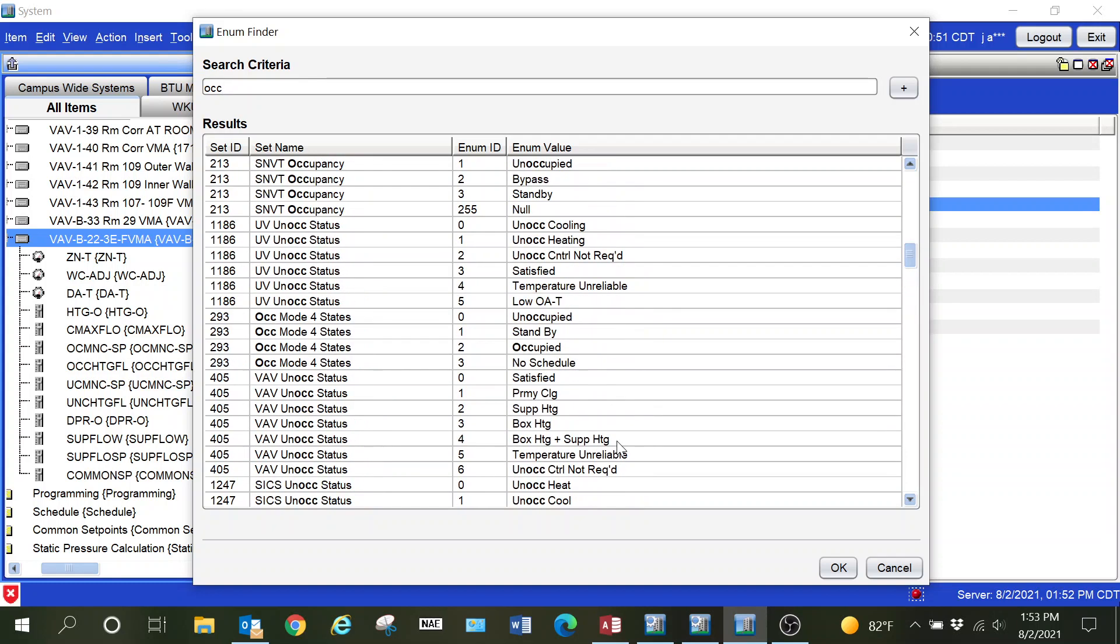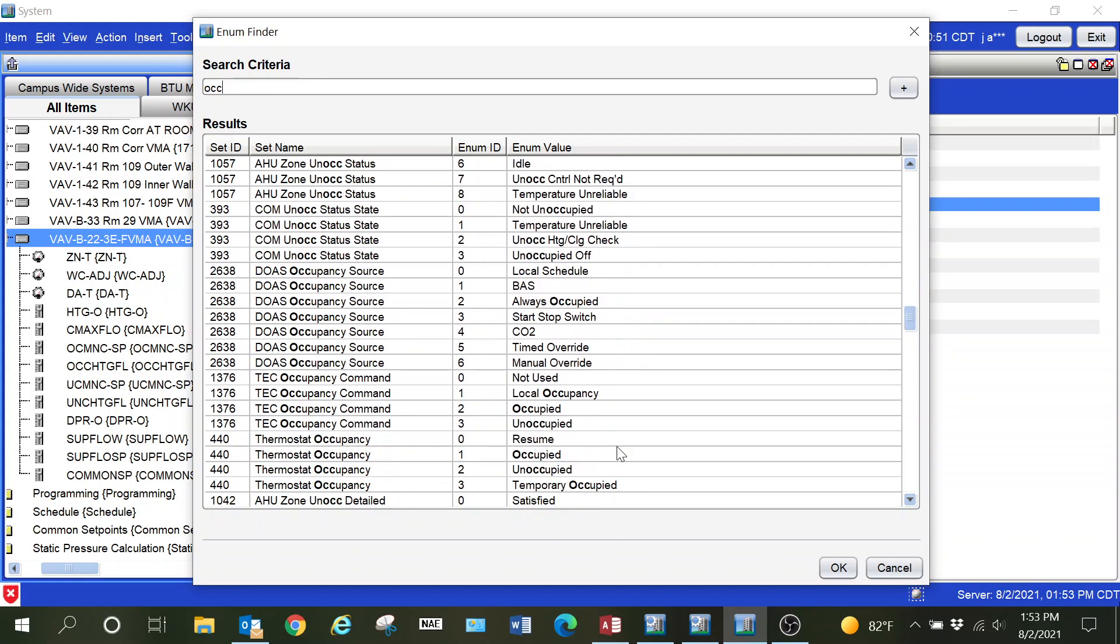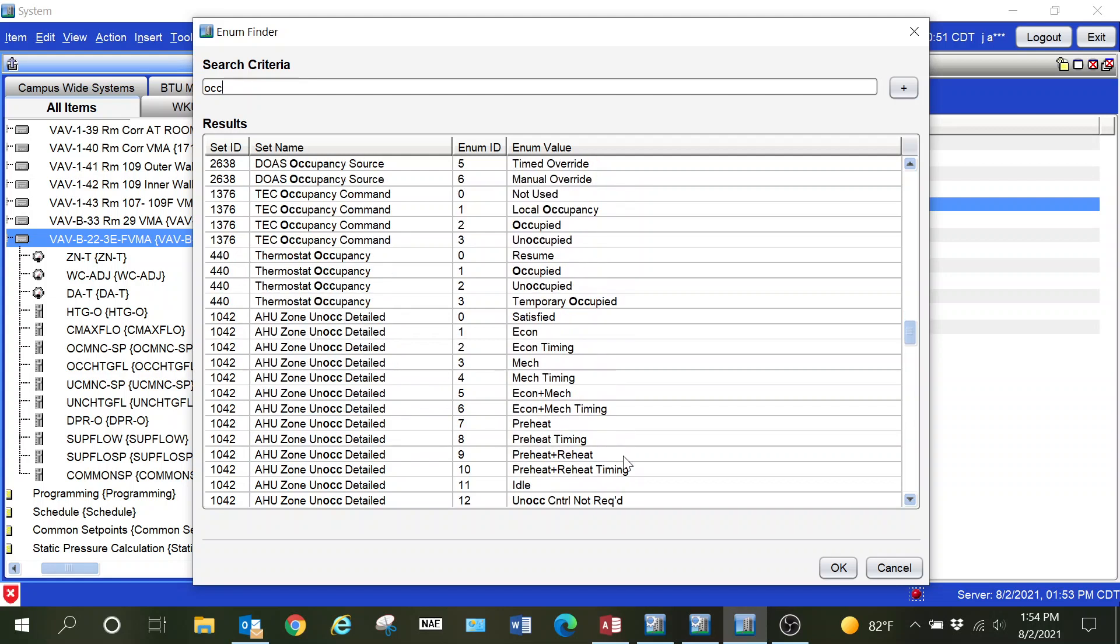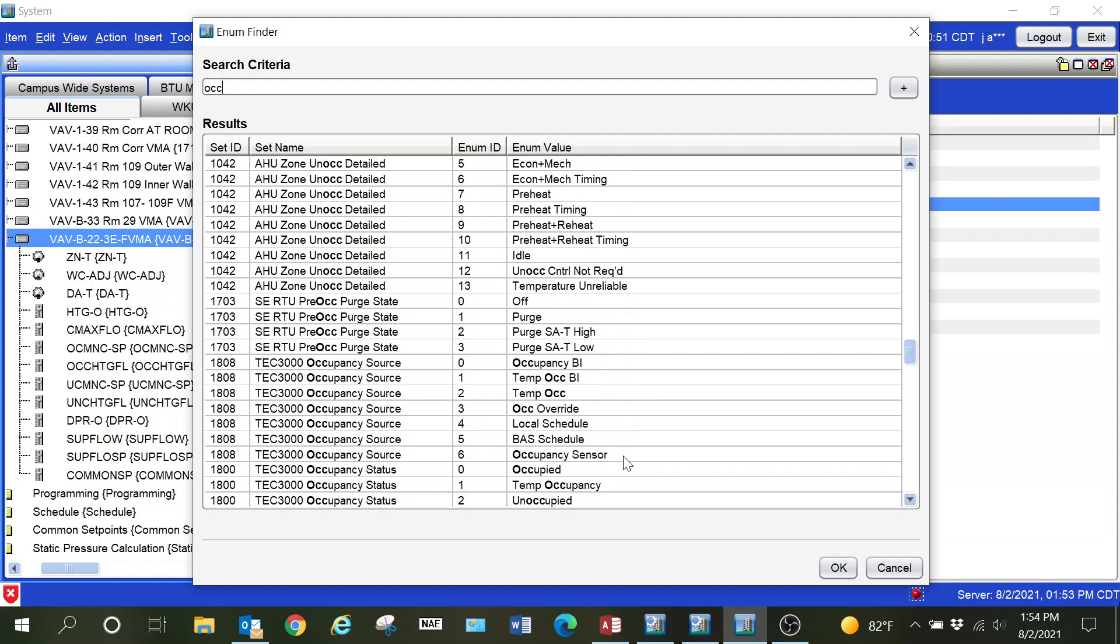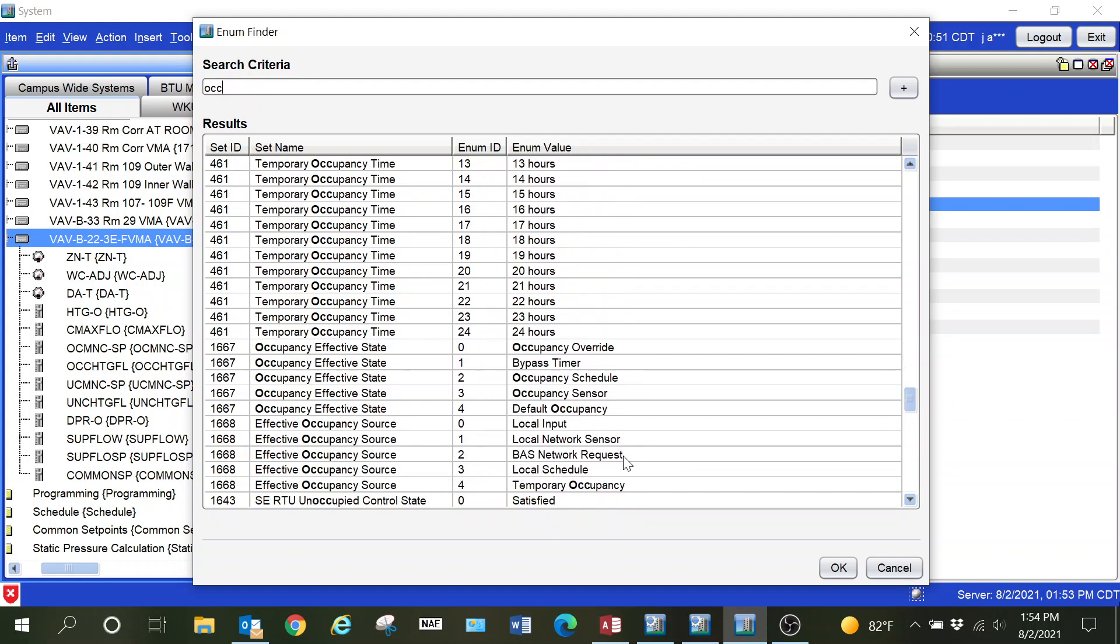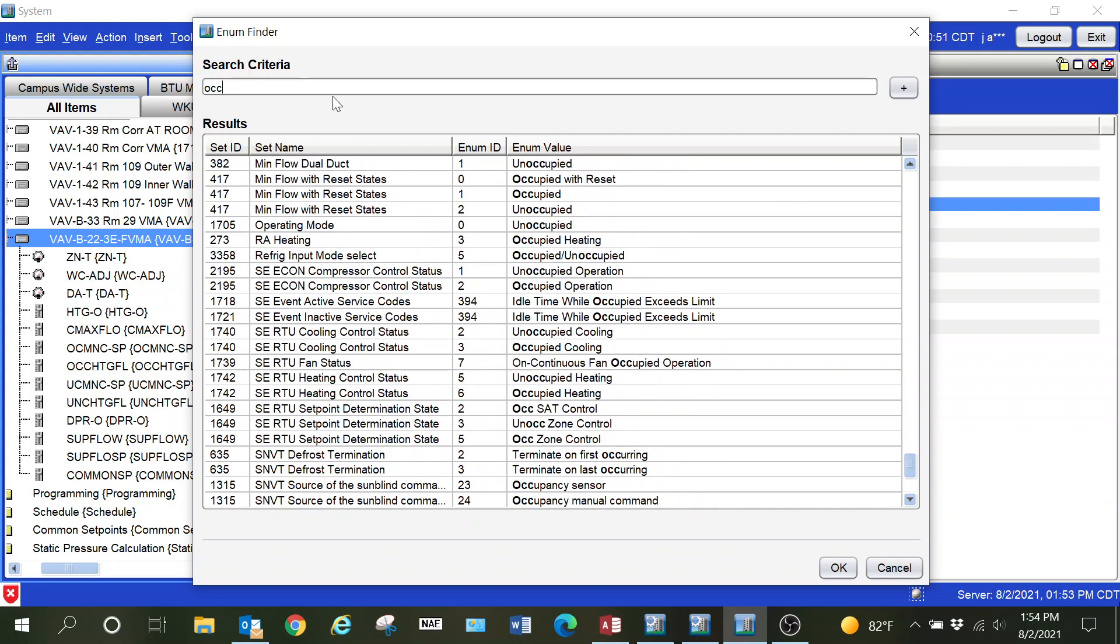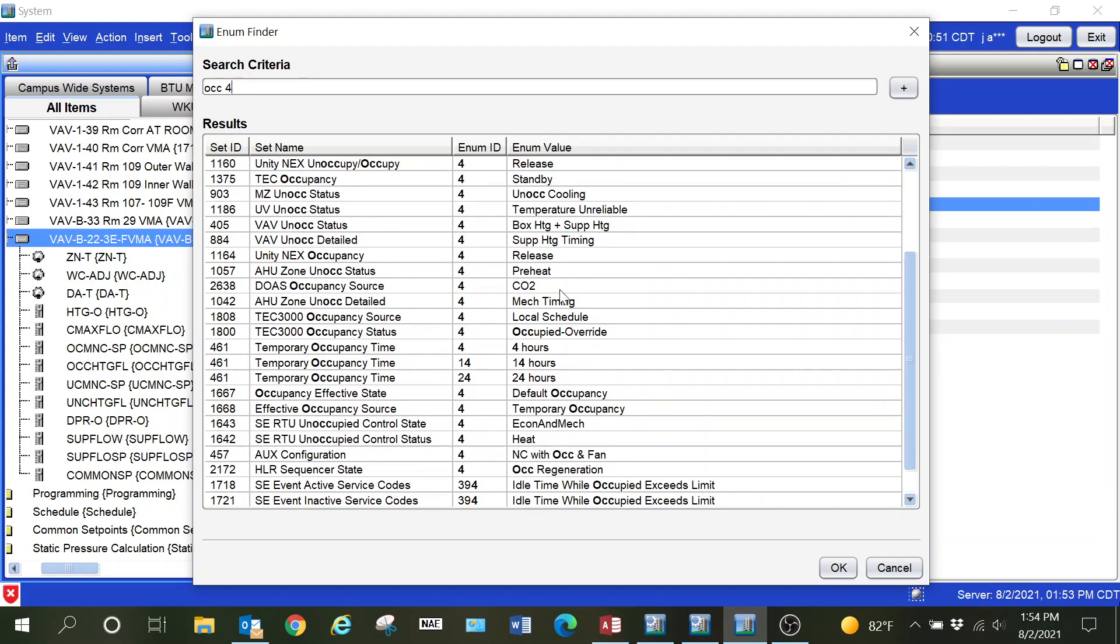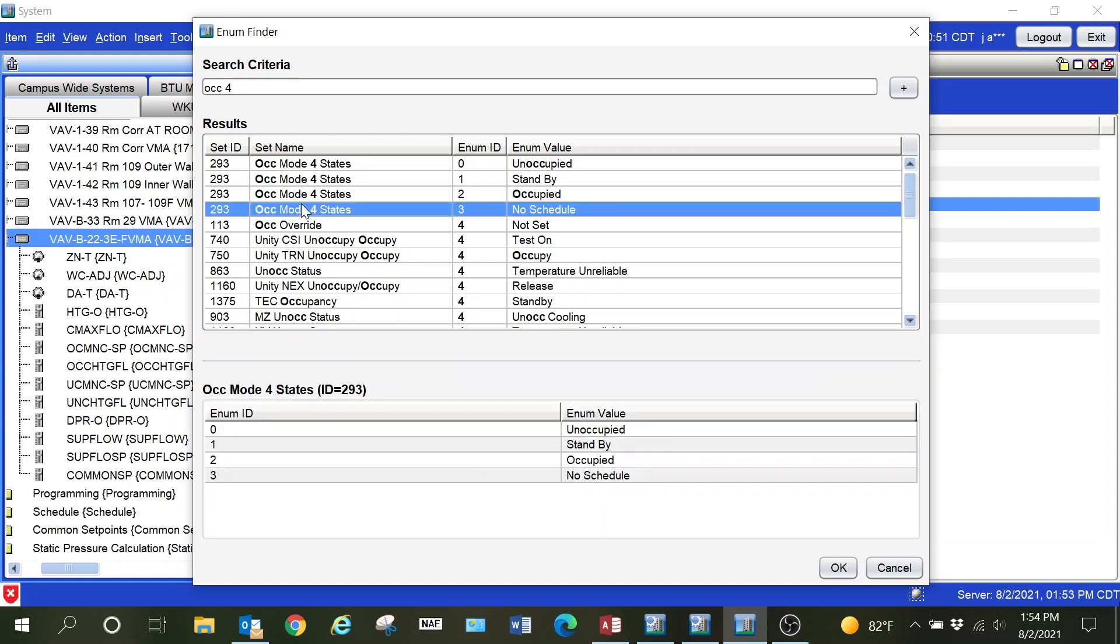That way our state text, instead of showing one, two, or three for occupancy, will actually give us a name. That way it is much neater and cleaner when you're going through troubleshooting. Depending on the controller and control point, you may not know what that value means. Taking just a few extra minutes and correcting the state text makes it much simpler.